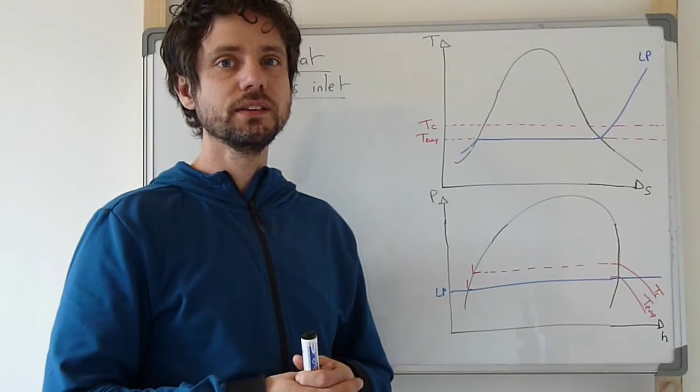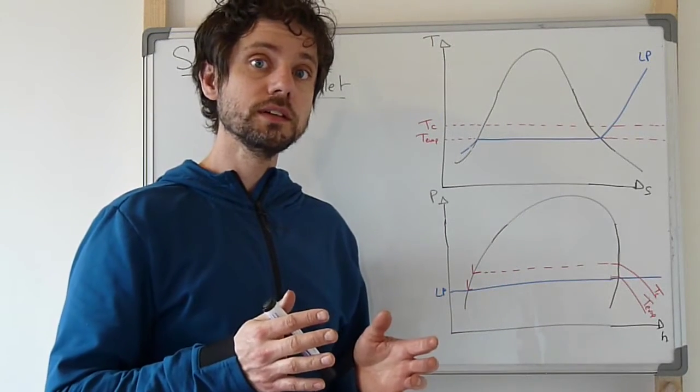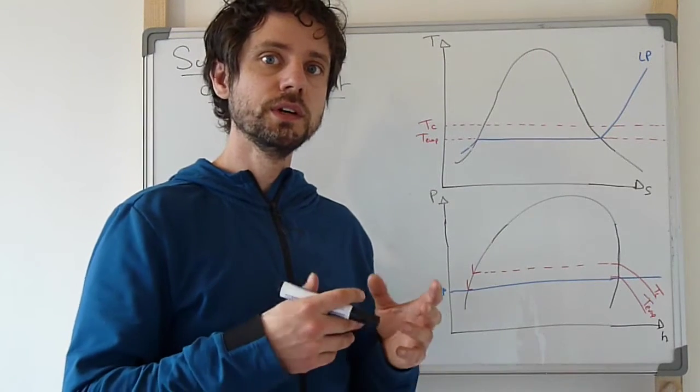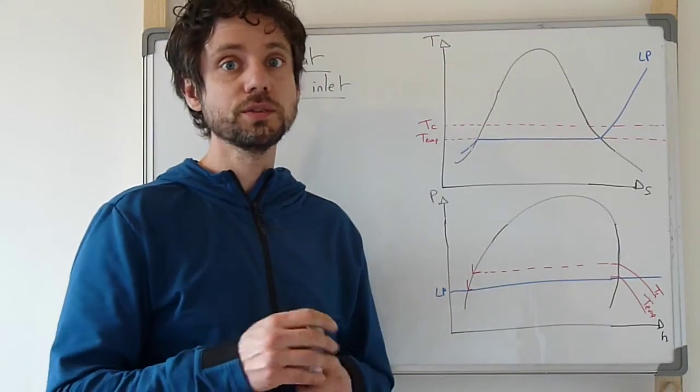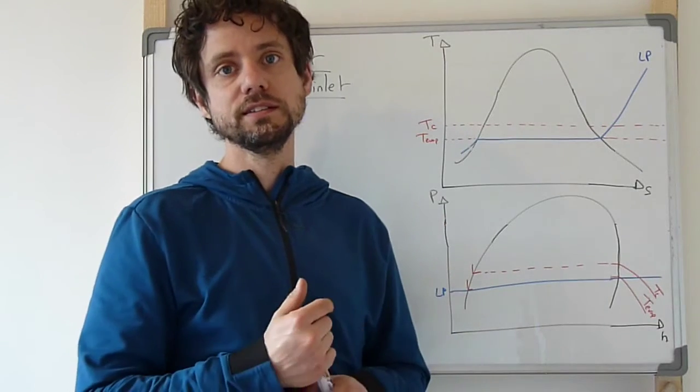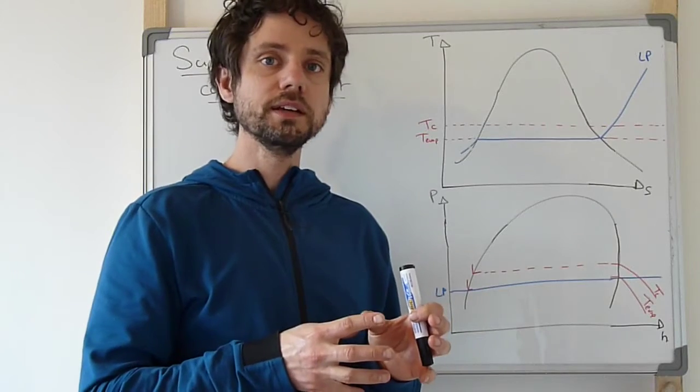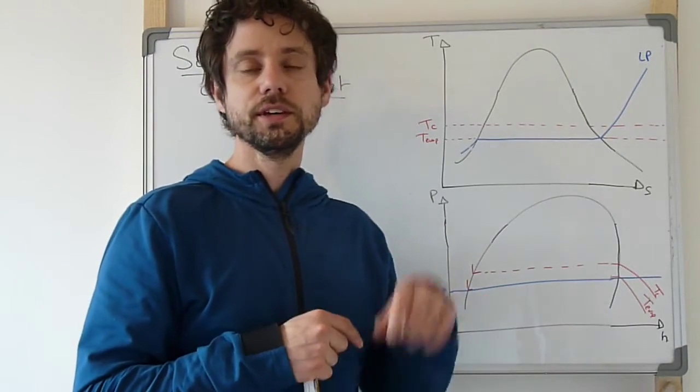In reality this is not exactly possible. The first reason is because the flow that is going out of the evaporator is usually not completely homogeneous. So if the average state is at saturation, there will be probably a mix of droplets and superheated vapors too.